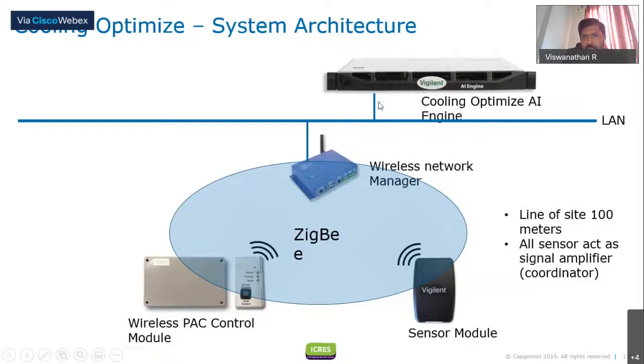The AI engine, in turn through the wireless network manager, communicates to the PAC control module to switch on, switch off, or modulate the PAC fans based on load, so there is no fixed PAC running to maintain the data center temperature. Instead, it is managed as per the temperature in front of the rack, sensed through this sensor module.